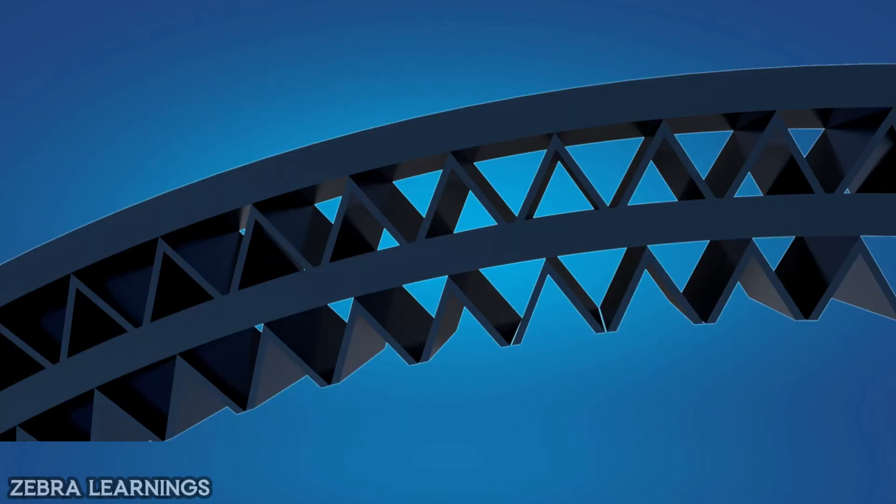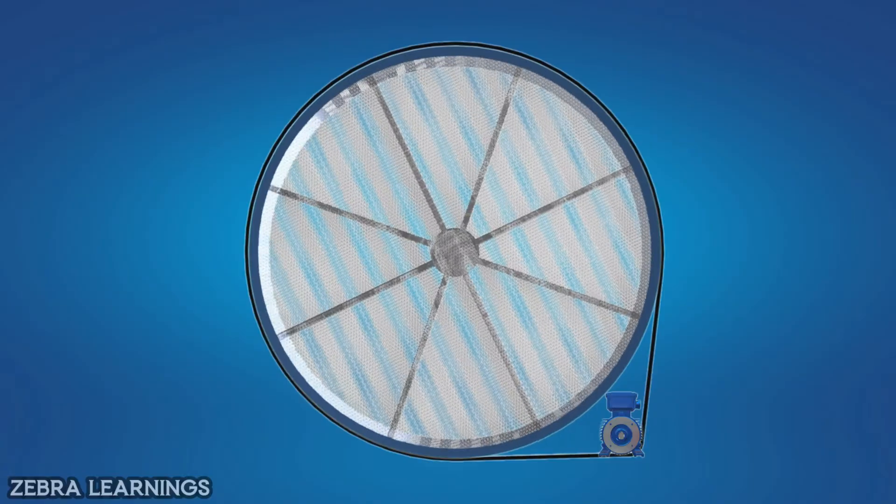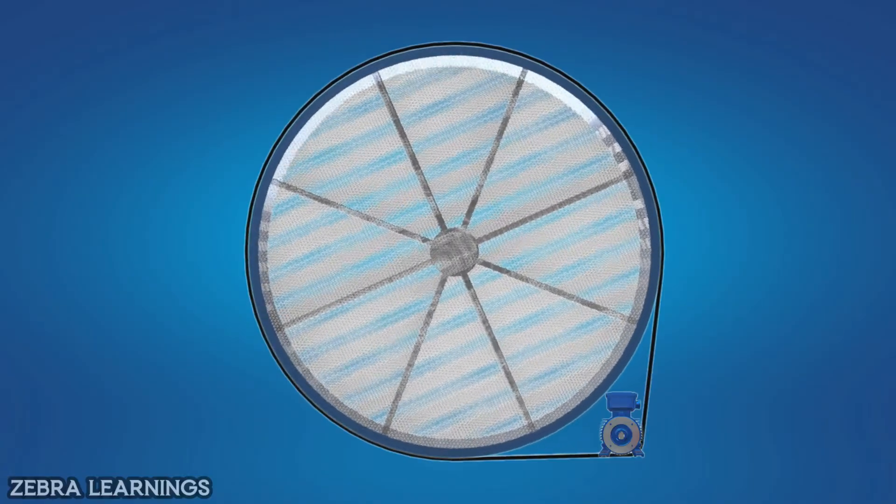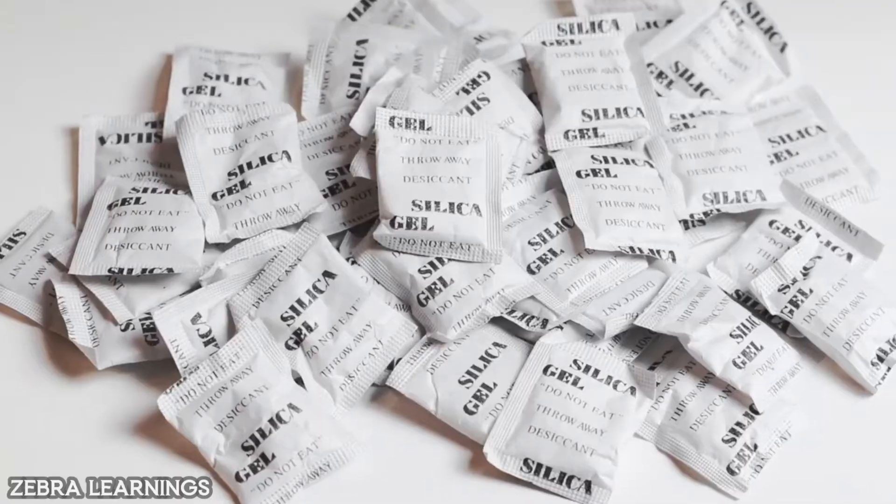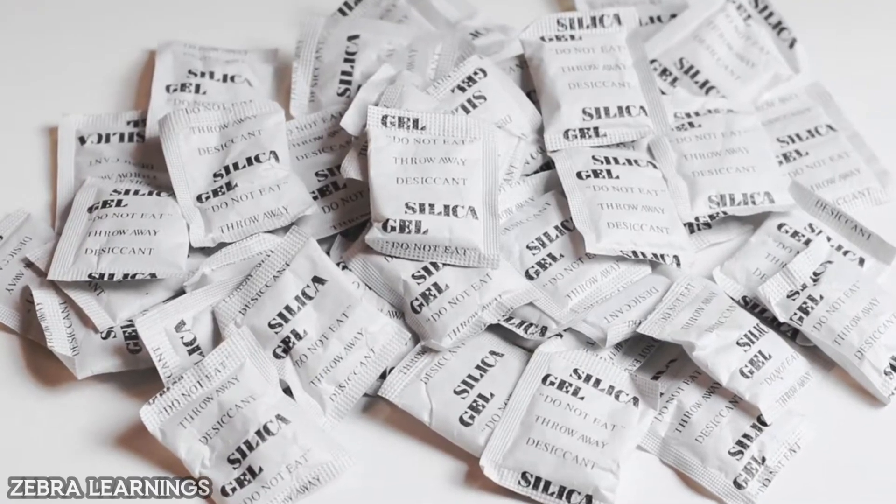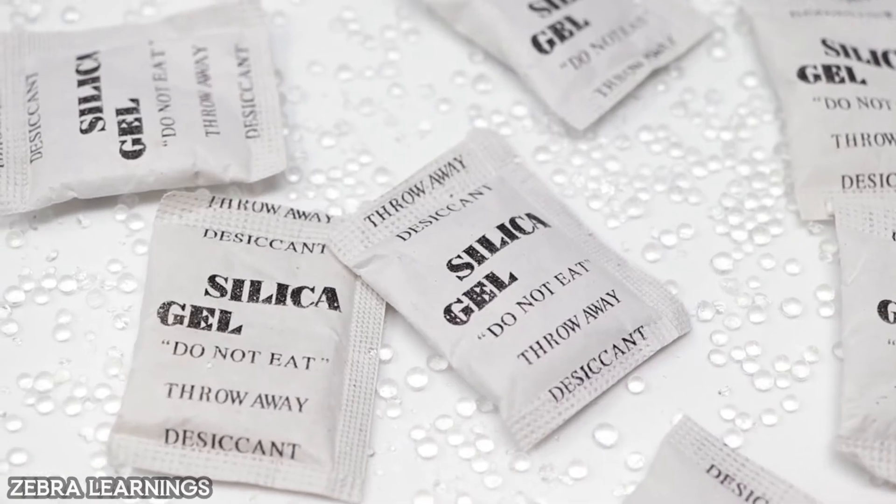This aluminum material is installed in fins type with small gaps so air can flow through it, and it has silica coating. The silica coating absorbs moisture from the air traveling through the wheel. We have seen this silica many times in products we buy.